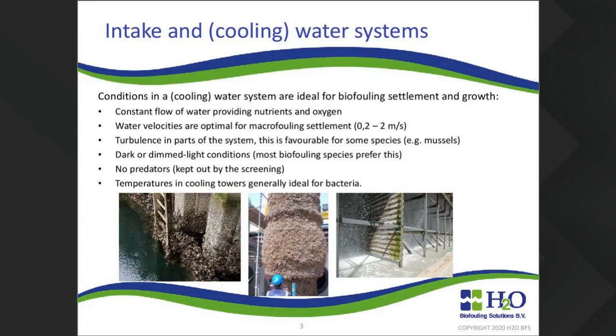There are no predators. Due to the screening at the inlet of an intake system, you keep most of the predators, like ducks, away from your cooling water system. So the animals have a very safe environment to settle and grow. In cooling towers, the temperatures are relatively high and provide an excellent condition for bacteria to settle and to grow into a biofilm.